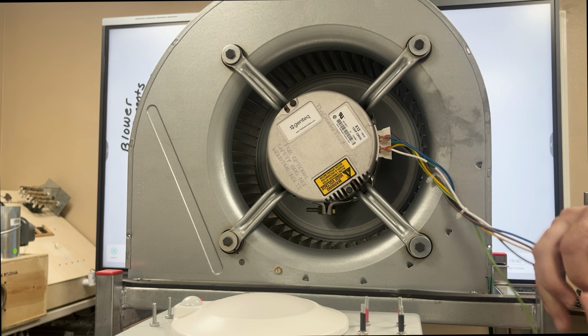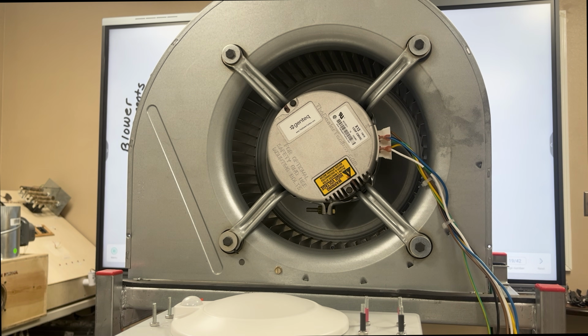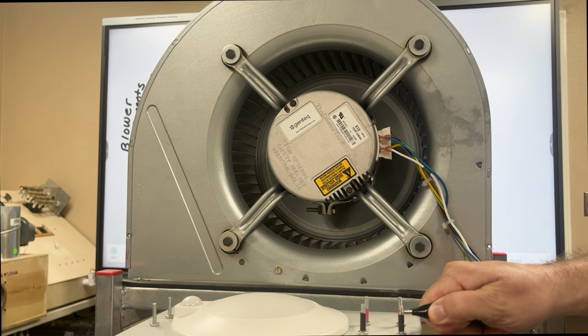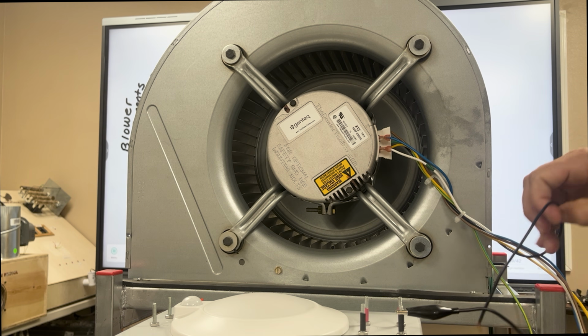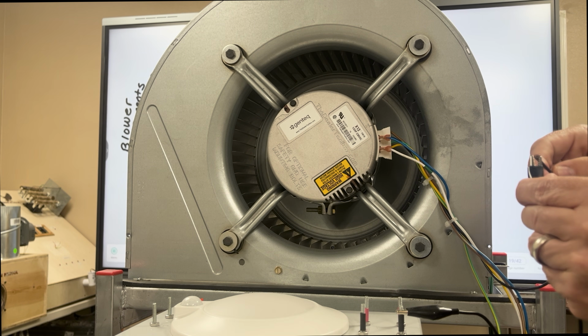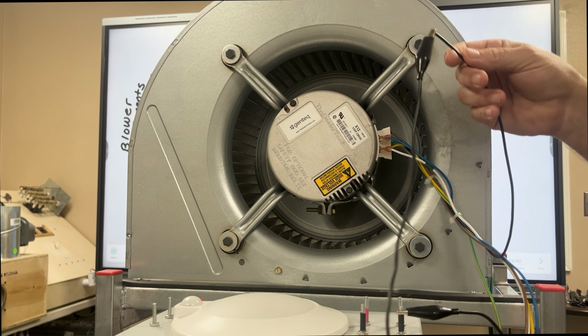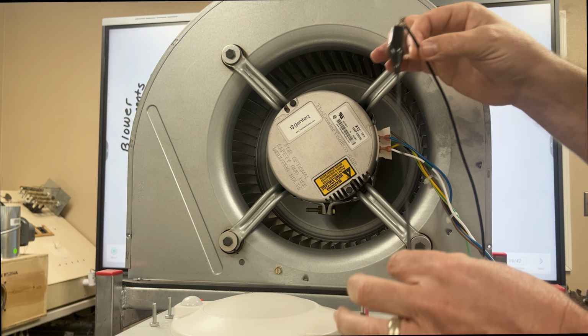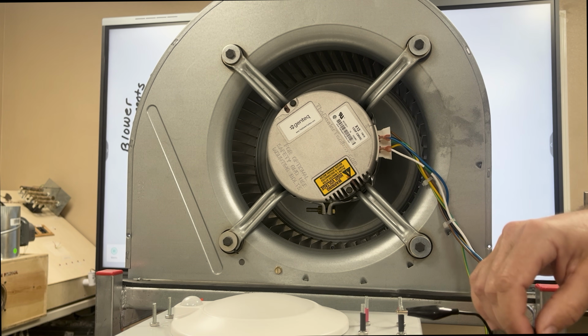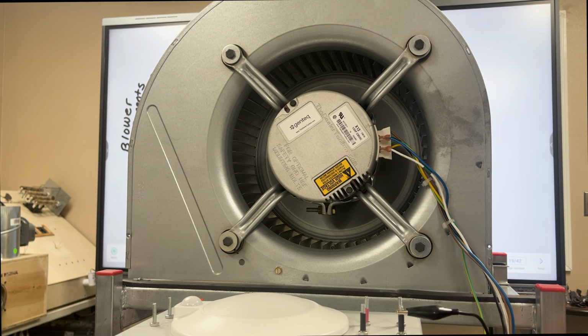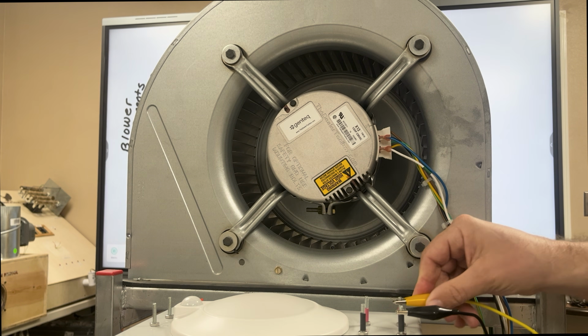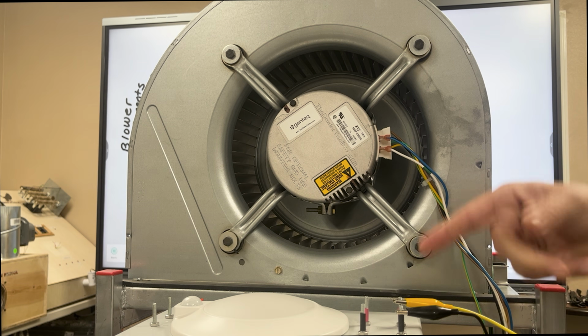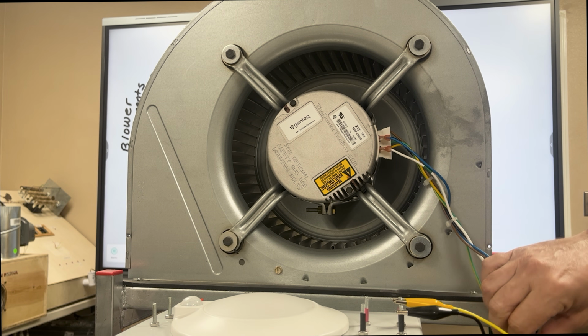And I'm going to show you real quick how easy this is. First, we're going to go ahead and wire up our line voltage. We're going to connect one leg to one high voltage side of our motor. As you can see here, I'm just going to let this dangle, so it might be off screen. That's okay. And then I'm going to take the other leg. Okay, so we have L1 and L2 now.